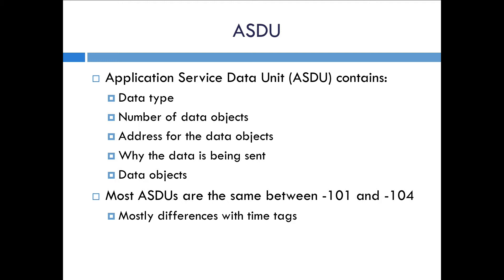These ASDUs are defined in the standard and built up with several different base types, so there are several standard ones defined. The spec also leaves open the possibility of creating custom ASDUs, though for interoperability that could be a limiting factor unless both sides recognize the same custom ASDUs. Note that 101 and 104 do have the same set of standard ASDUs — they're basically the same, with the biggest difference being in the time tags, where the format for those is different.